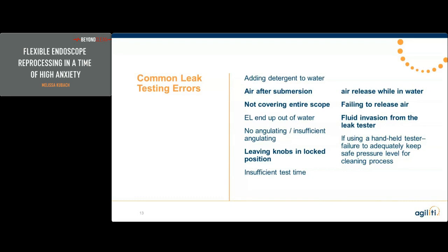I also see, especially with one of the more current models that now has a self-venting valve and does not have a waterproof cap, failing to release all of the air pressure by allowing enough time can cause fluid invasion problems. It may only open that valve for a split second, but it can take just a little bit of moisture in over and over until it has caused a great amount of damage. It may take a while to show, but it will come around.